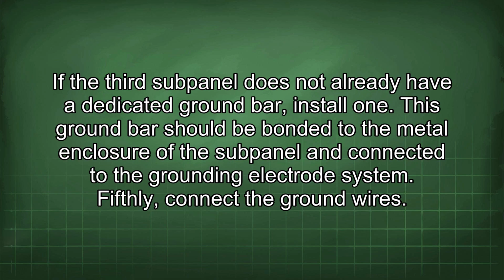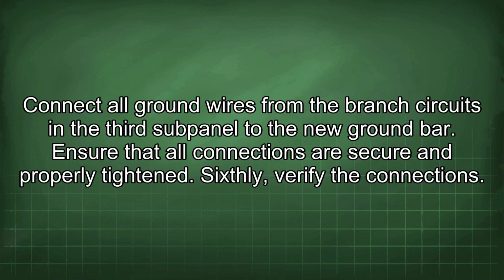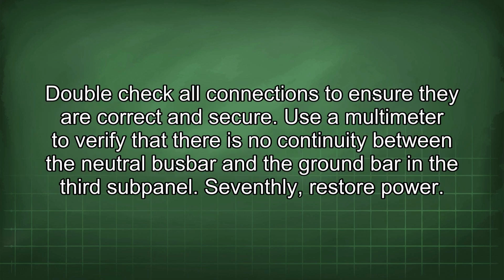Fifthly, connect the ground wires. Connect all ground wires from the branch circuits in the third subpanel to the new ground bar. Ensure that all connections are secure and properly tightened. Sixthly, verify the connections. Double check all connections to ensure they are correct and secure. Use a multimeter to verify that there is no continuity between the neutral busbar and the ground bar in the third subpanel. Seventhly, restore power.